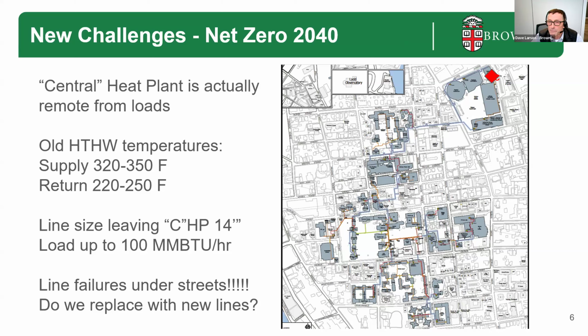You may be able to make out these lines, the high temperature hot water lines that snake through campus feeding the different loads. It's a high temperature hot water system. Before our thermal efficiency project, supply temperatures ran anywhere from 320 to 350, with a 100-degree delta T, and fairly small lines leaving that remote central heat plant, only 14 inches. We're not as big as the other institutions talking today, a bit of a smaller university, but only a 14-inch line because we relied on that high delta T.